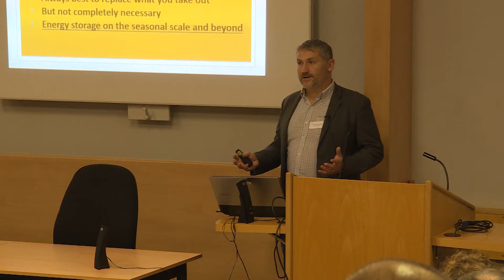The one thing I would say is you do get groundwater flow across the site. In some sites it's nothing at all because the groundwater's at depth. In other sites it's not very much because it's clays or very low permeability rocks. On other sites, where you may have pumping stations nearby, you can have very significant amounts of groundwater flow across your ground loop. When you've got closed loop systems, that can either help or hinder.